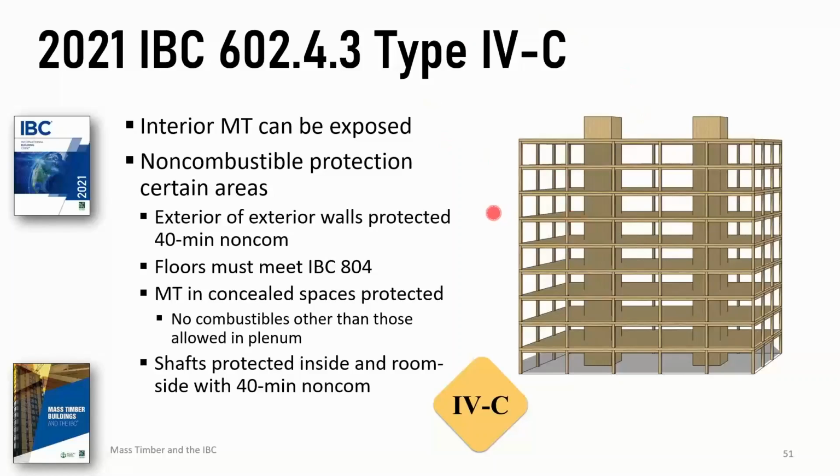Why can the interior be exposed? Well, it's living area. It's viewable. We know where the fire is. We know how to address it. In almost every case, the sprinklers will address it, but if not, it's visible. People will leave, the fire will burn. It won't be traveling through spaces of the building that can't be seen.